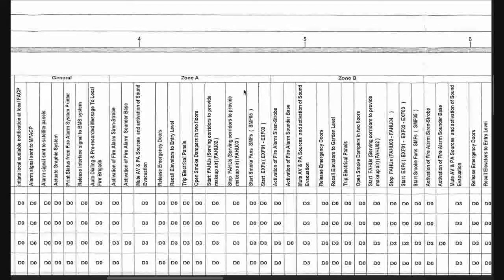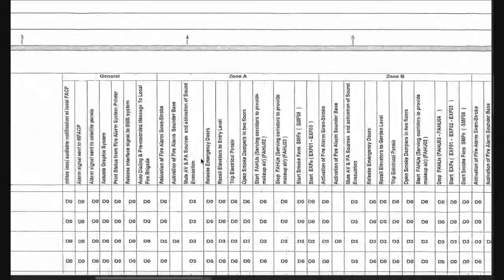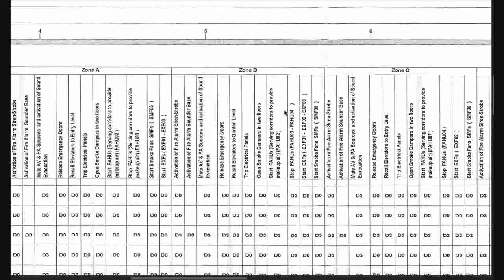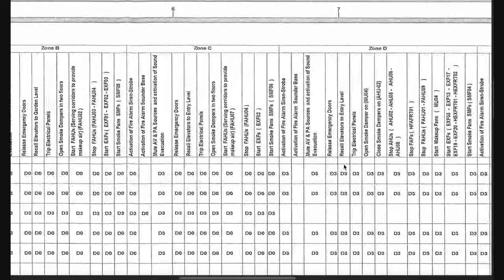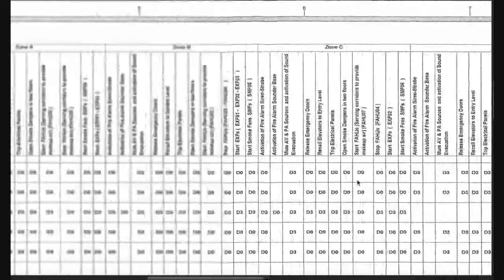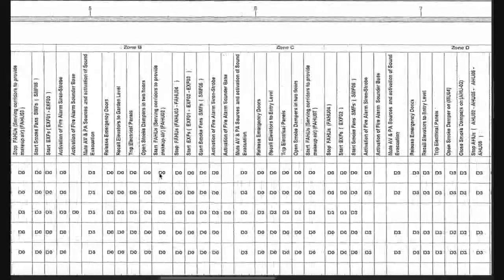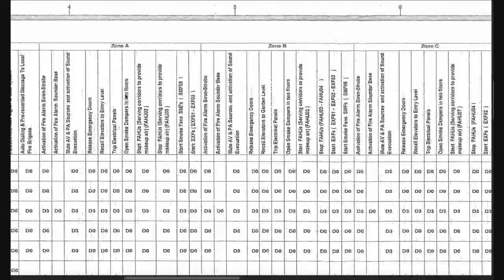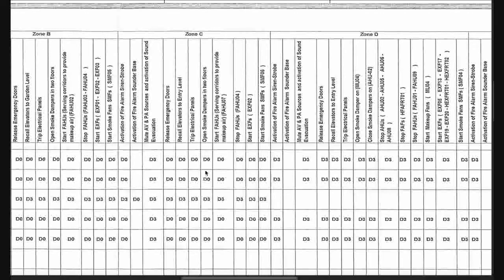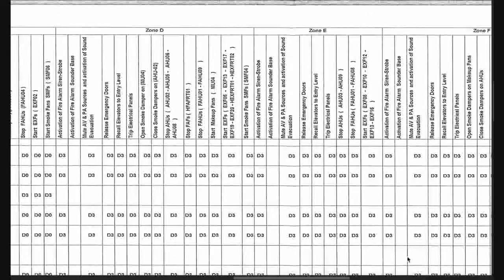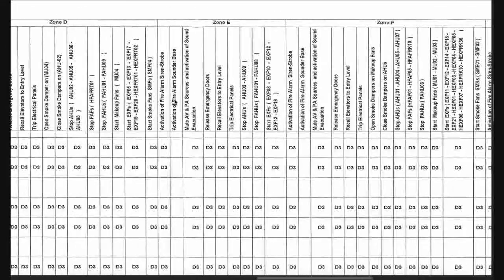The same scenario is repeated for each zone. So, in each zone, if we have a fire in Zone A, what will happen in the other zones? If the fire is in Zone A and activated by a normal smoke detector, we have immediate actions in Zone B and Zone C — they are the neighbors of Zone A. But in Zone D, actions are delayed by 90 seconds because it is not a close zone.